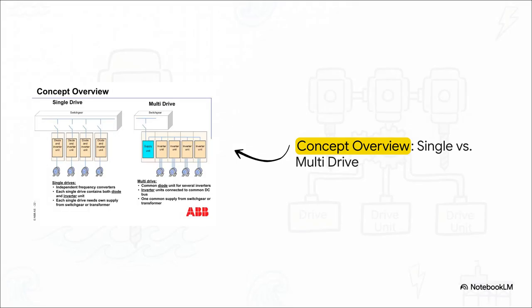So just how much floor space and raw steel does each of these topologies actually demand? Well, with a single drive system, you have completely independent frequency converters. Basically, each one packs its own diode and inverter unit, meaning each drive needs its very own dedicated supply. But on the flip side, the multi-drive setup takes a totally different approach. It uses one shared supply unit that feeds a common DC bus. All the individual inverters just tap directly into that single shared line.